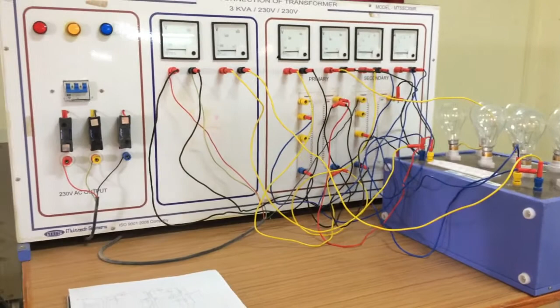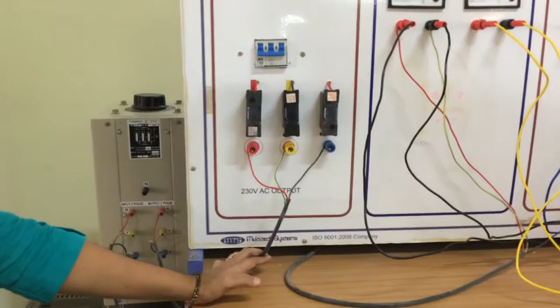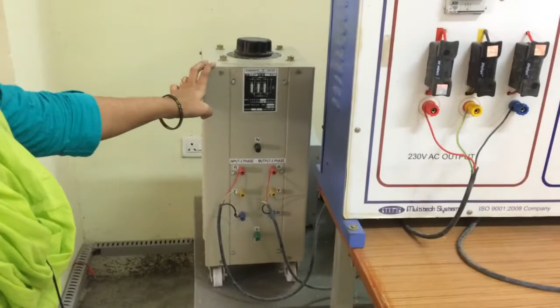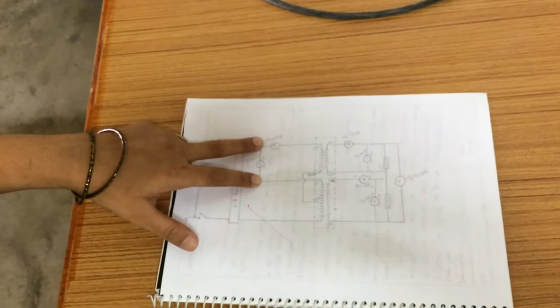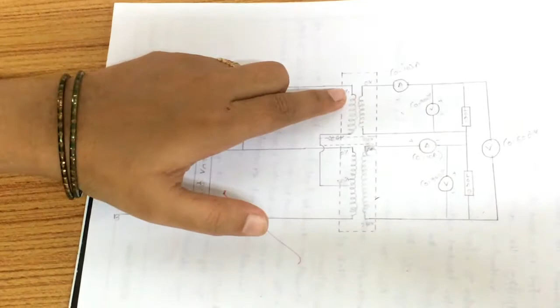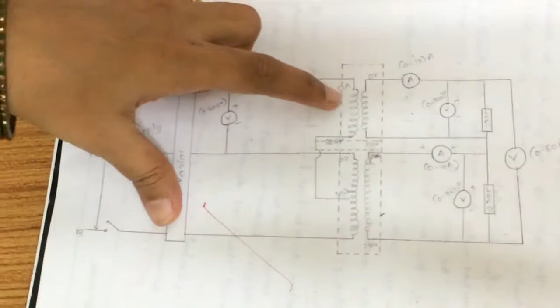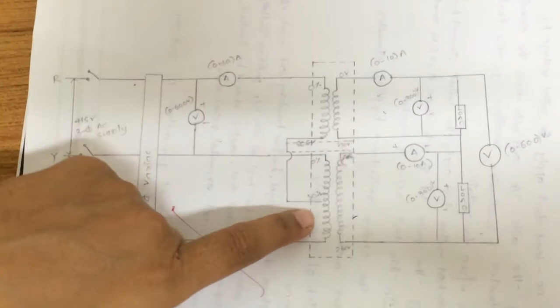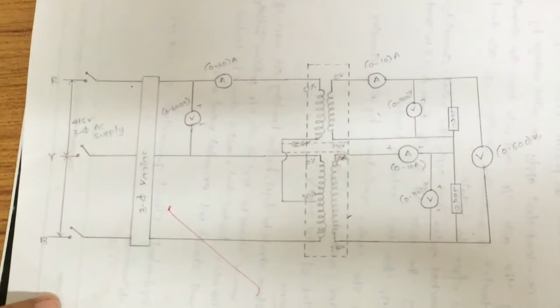Now let us see the connections of the Scott connection of transformer. This is the MCB, these are the fuses related to this panel board, and these are the AC output terminals. From these AC output terminals, connections are given to the three-phase variac, and the output of the three-phase variac is given to the voltmeter. The connections are made as per the circuit diagram. You can see that across 2 phases we need to connect a voltmeter. Consider the left side as the teaser transformer primary and secondary, and the right side as the main transformer primary and secondary. From the 86.6% tap of the teaser transformer primary, connection is given to 50%, and then the 0% of the teaser transformer primary is connected to Y, with the connections made as per this diagram.